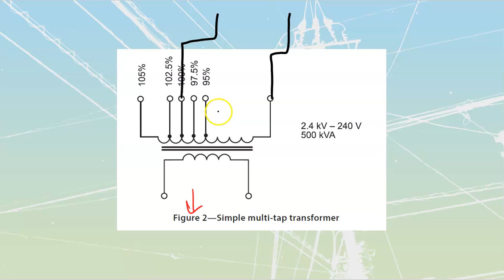Over here on this side, I know that I'm getting too little voltage out. Usually the taps are going to be on the high voltage section. Why? Because the high voltage section is going to have smaller amounts of current, right? And smaller current connections are easier for us to deal with than large current connections. Otherwise, you have to worry a lot more about heat and transformers, conductor size and everything like that. So usually we change on the high side.